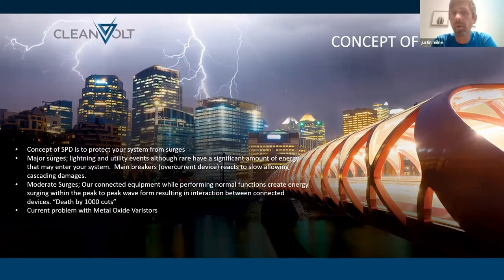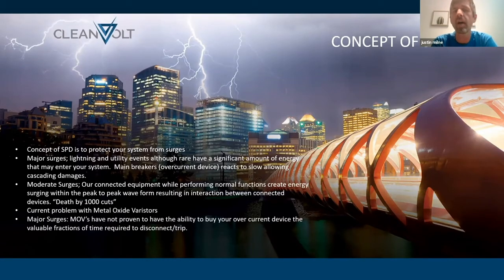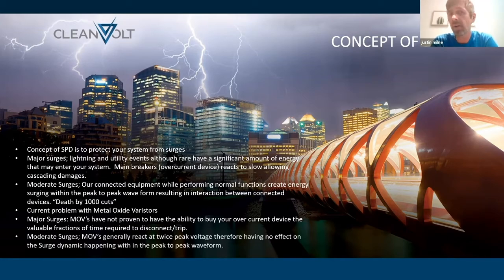So the current problem with metal oxide varistors is that, one, when it comes to major surges, they have not proven to have the ability to buy your main overcurrent device the valuable fractions of seconds required to disconnect you from the incoming event. And when it comes to moderate surges, because they react at 2 to 3 times peak voltage, they're having little to no effect on the actual surge dynamic happening within the peak-to-peak of the waveform.